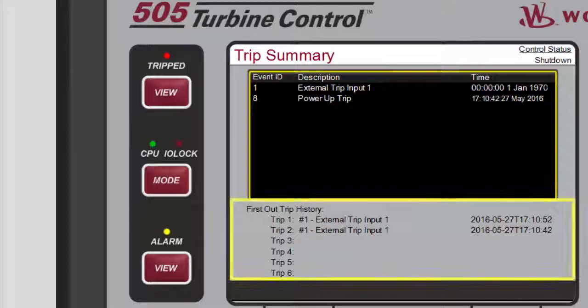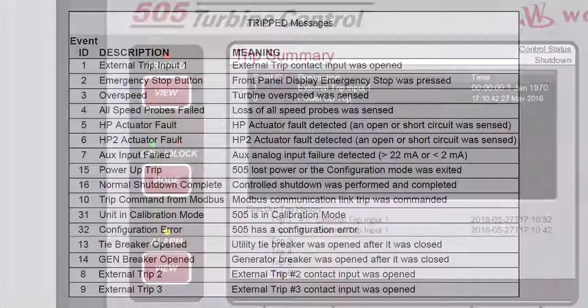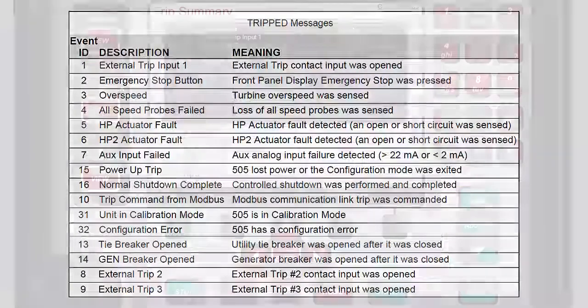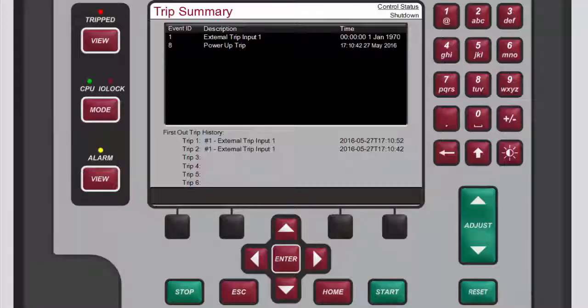In addition, the first-out trip history at the bottom of the page lists the last six first-out trips. This is useful for viewing the history of trips even after the trip condition has been cleared. The 505 manual describes all shutdown event IDs in the tripped messages table. To return to the last screen you were on, press View again or press Escape.